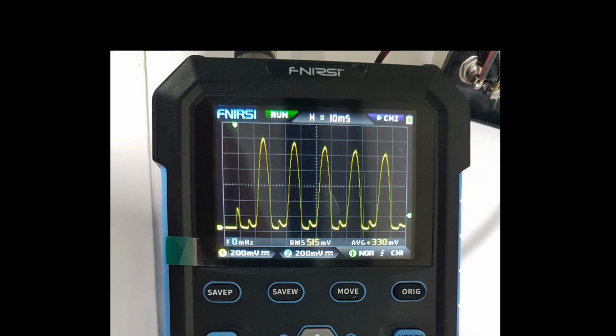The big difference on this machine is, while a heart monitor slowly moves from the left to right, this can do it really fast. So a heart monitor, to go from the left to the right of the screen, takes a couple of seconds. The horizontal blocks are in 10 millisecond increments. The vertical blocks are 0.2 volt increments. So the bottom left corner is 0 seconds, 0 volts. As the time passes, it will start to record the voltage and it will plot it on this graph. The result is that at the end of the day, we can see the voltage as a picture and not only as a value. This allows us to judge the stability of the voltage and not only its magnitude.